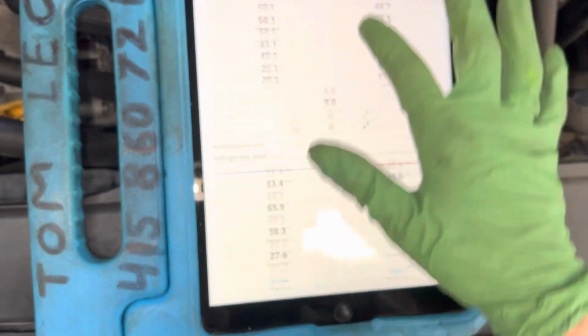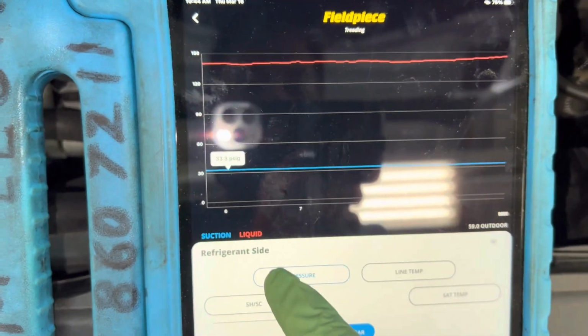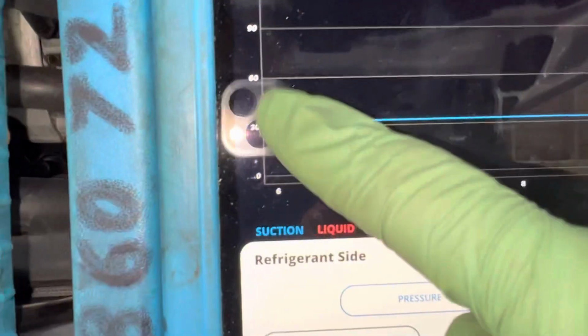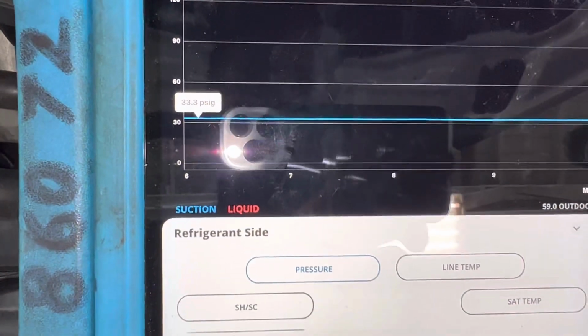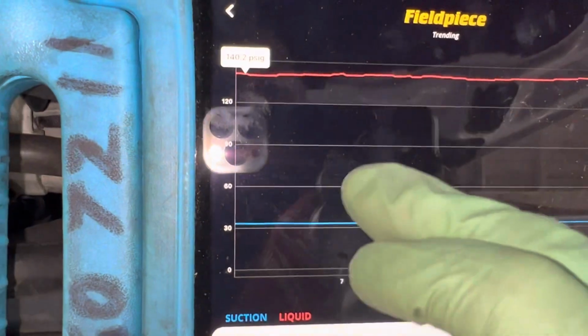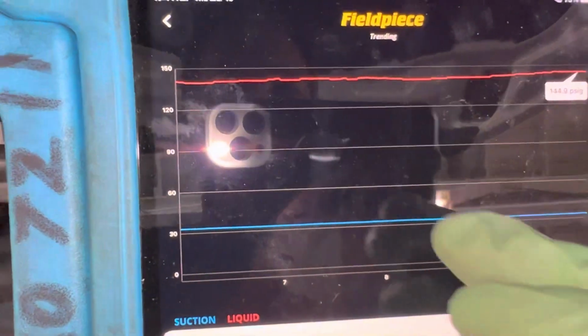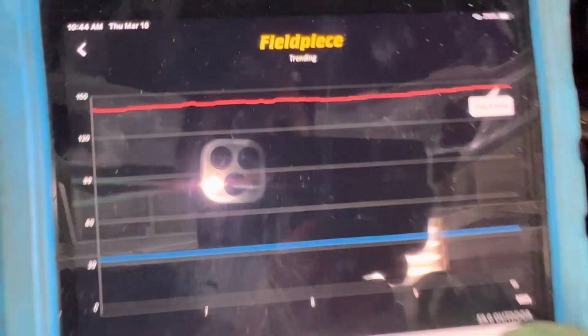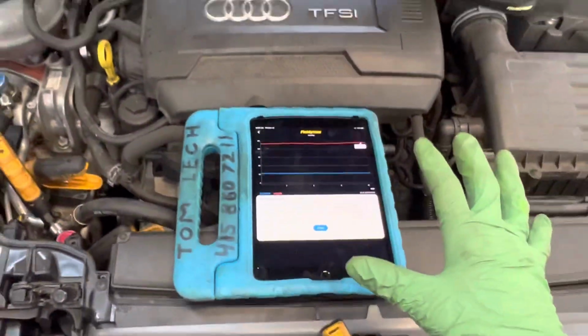What else do we have here? Let's go back to our pressures. Our low side pressure has been staying rock steady at 33 psi, 33.4, 33.3, absolutely no movement at all. The high side pressure has been staying between 140 and 144, nearly no movement at all.